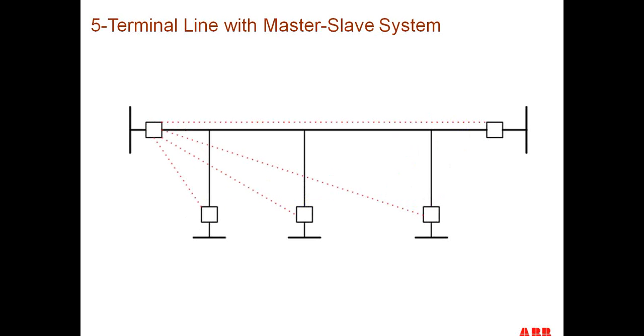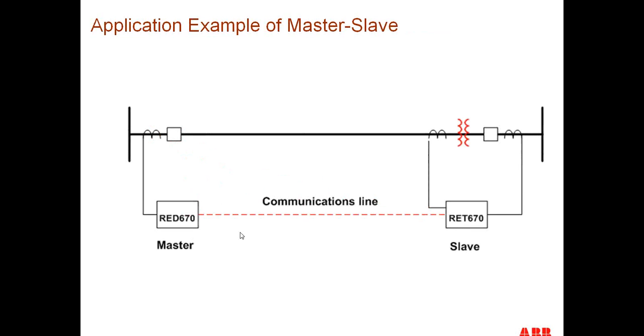Another method of doing this to save communications is master-slave communications. In this way, one relay becomes the master, and it receives current information from each of the other relays, does the current differential calculation, and then sends trip information back to the other relays if it decides that it needs to trip. Of course, if this relay goes bad, then this won't work. But it's a good way to save on communication channels if you don't have enough channels to connect all the relays to each of the other terminals. Our relays happen to have a separate communications card that you're able to put into any of the other relays. Here's an example of a master-slave that's been done before.